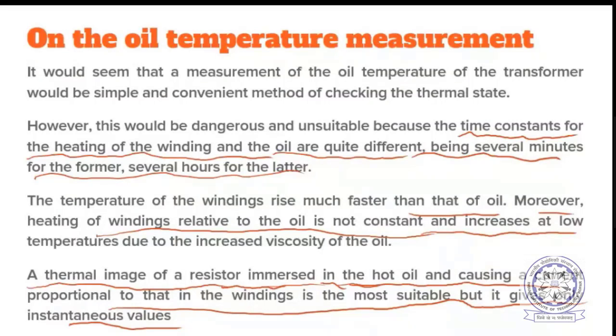Because the current flowing through the resistor is proportional to the winding current, the temperature of the resistor gives an indication of the winding temperature. You can always calibrate the winding temperature. But it gives only the instantaneous value of the temperature of the transformer. So, instead of measuring oil temperature, a resistor may be immersed in the hot oil, with a current proportional to that of the windings. If you somehow arrange that a proportional current that flows through the winding is allowed to flow through the resistor, then the temperature is also proportional to what occurs in the windings. This way we can measure the instantaneous value of the temperature of the winding. By calibrating the measurement system, we can exactly find out the winding temperature using this method.